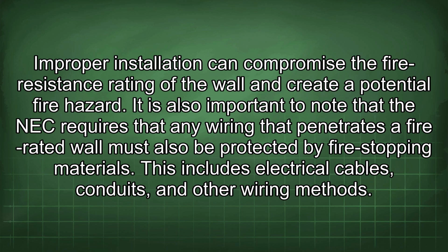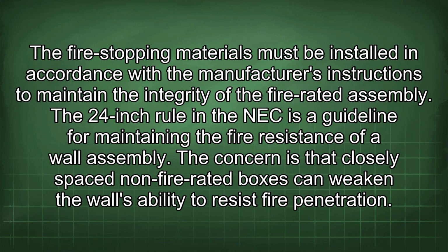It is also important to note that the NEC requires that any wiring that penetrates a fire-rated wall must also be protected by fire-stopping materials. This includes electrical cables, conduits, and other wiring methods. The fire-stopping materials must be installed in accordance with the manufacturer's instructions to maintain the integrity of the fire-rated assembly.